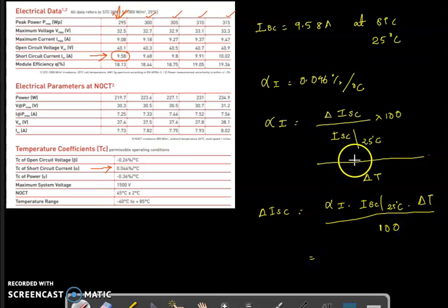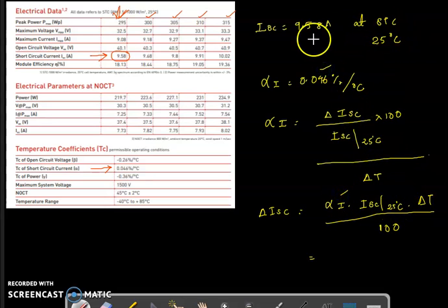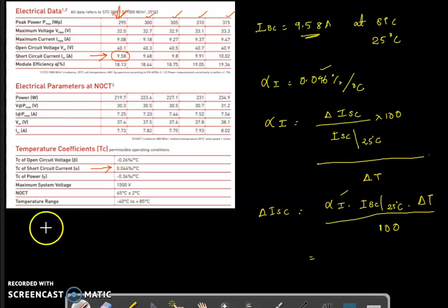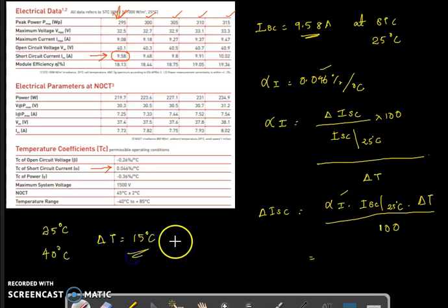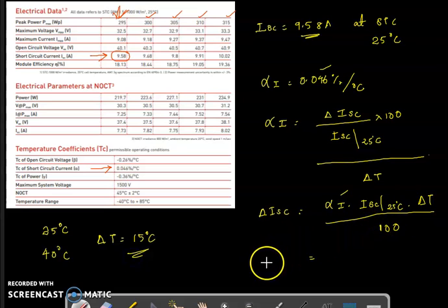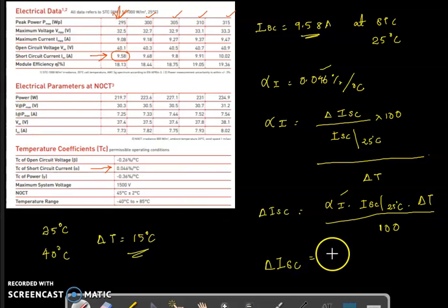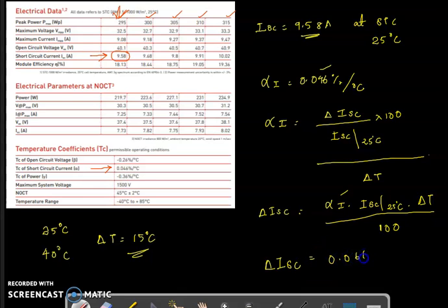By substituting the value of alpha_i and the short circuit current of 9.58, along with the change in temperature — since the standard test condition is 25 degrees Celsius and we want 40 degrees Celsius, the change in temperature is 15 degrees Celsius — we can find the change in short circuit current. Substituting all these values gives a change in short circuit current of 0.066 amperes.